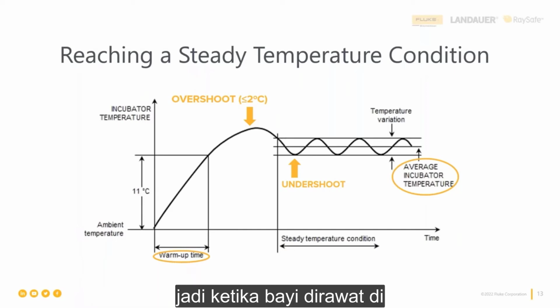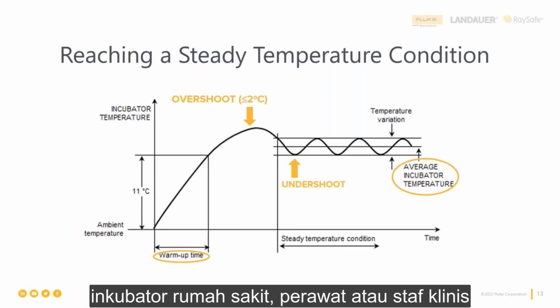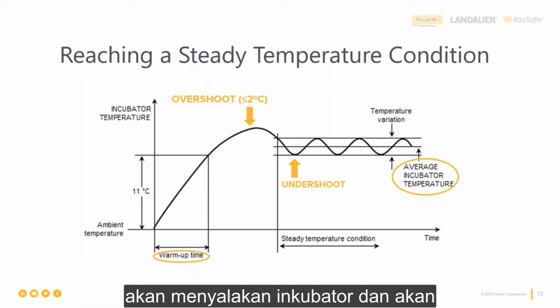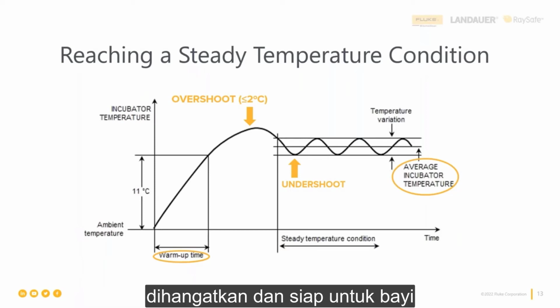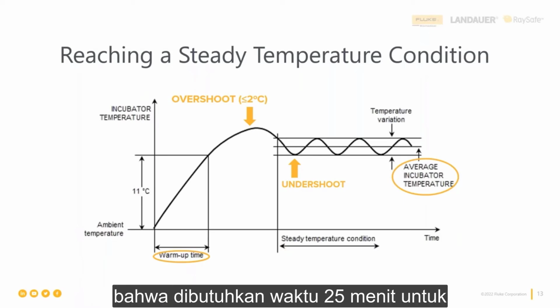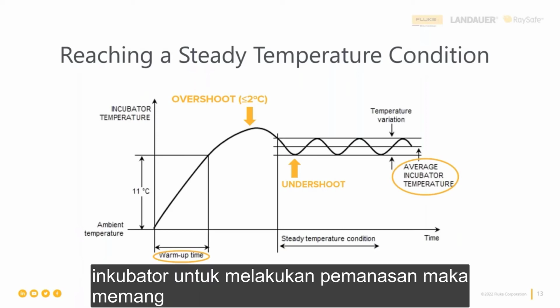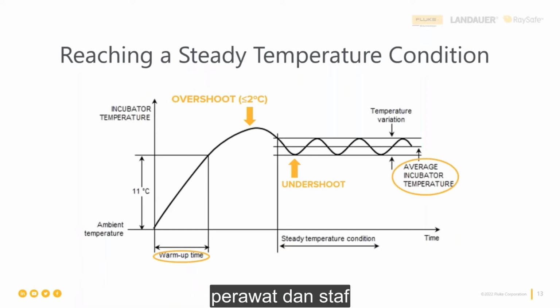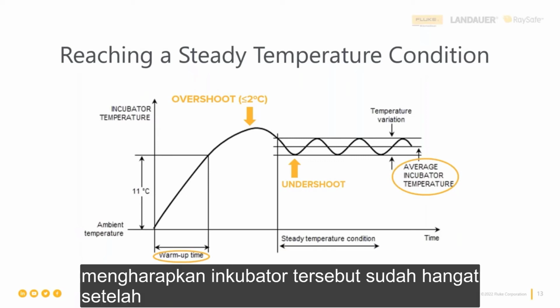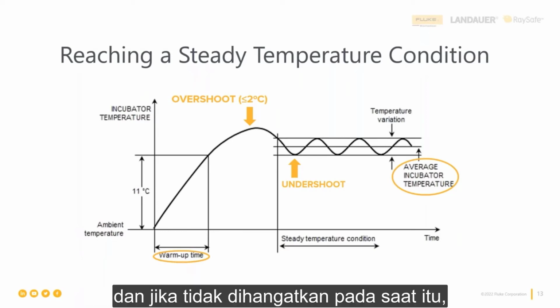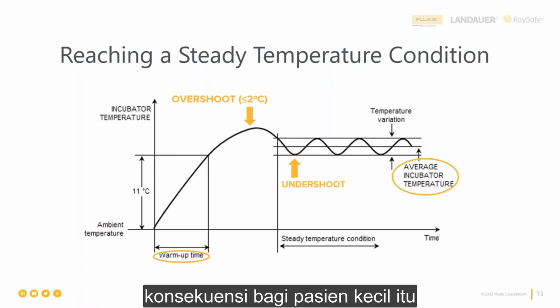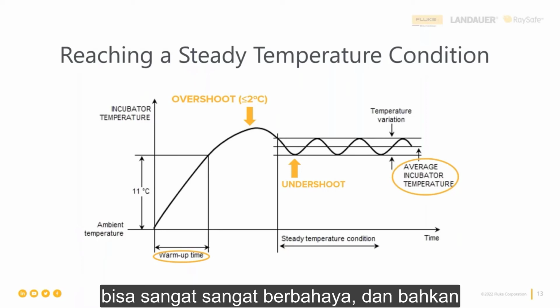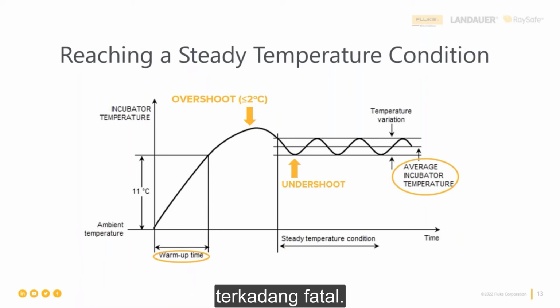When a baby is being admitted to an incubator, the nurses or clinical staff will turn on the incubator and have it warmed up and ready for the infant to be placed inside of it. So if the manufacturer's manual states that it takes 25 minutes for the incubator to warm up, then indeed the nurses, the staff, and the little patient that goes inside the incubator will expect that incubator to be warmed up at the end of those 25 minutes. And if it is not warmed up in this time, the consequences for that little patient can be very, very dangerous and even fatal at times.